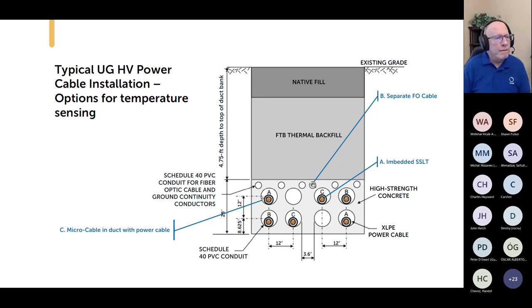So what happens is, when the circuit's carrying power, the conductor's going to heat up, and then that heat has to dissipate. But before it gets to this cable, it's got to go out of the power cable, through the air, through the conduit, into the concrete, through some more conduit, and then through the jacket of your sensor cable, and then to the fibers themselves. So that heat is slowly degrading through that penetration process. It's dissipating. So the temperature I'm going to read here is going to be significantly lower than the temperature I read here. And that's not a good thing if you're really concerned about the reliability of this cable. And there's going to be a significant time lag. It takes time for that heat to penetrate from the power cable into the optical fiber cable.